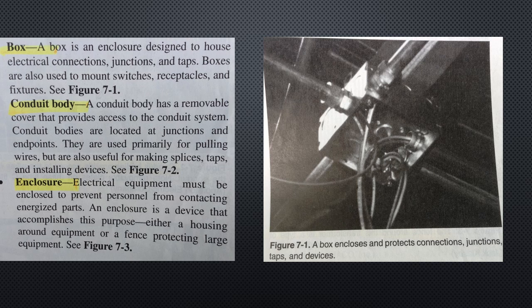The code requires all conductor joints, connections, taps, and splices to be housed inside approved enclosures. Boxes provide protection from both fire and shock. Article 314, outlet device, pull and junction boxes, conduit bodies, fittings and handhole enclosures contains the code rules in this area.